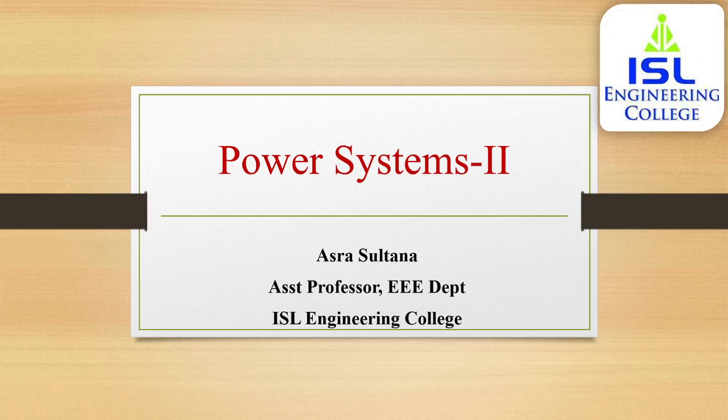Transformer in the system should be represented by a reactance in series. Find the total percentage reactance of the network up to the point of fault. Let it be X percentage. Find the full load current corresponding to the selected base kVA and the normal system voltage at the fault point.